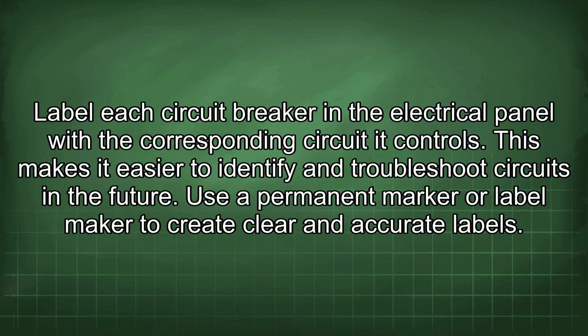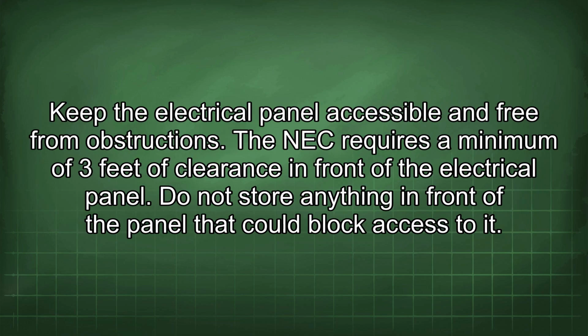Label each circuit breaker in the electrical panel with the corresponding circuit it controls. This makes it easier to identify and troubleshoot circuits in the future. Use a permanent marker or label maker to create clear and accurate labels. Keep the electrical panel accessible and free from obstructions. The NEC requires a minimum of 3 feet of clearance in front of the electrical panel. Do not store anything in front of the panel that could block access to it.